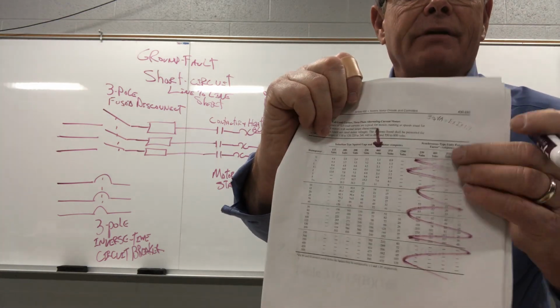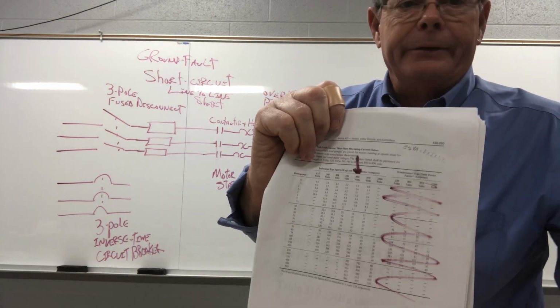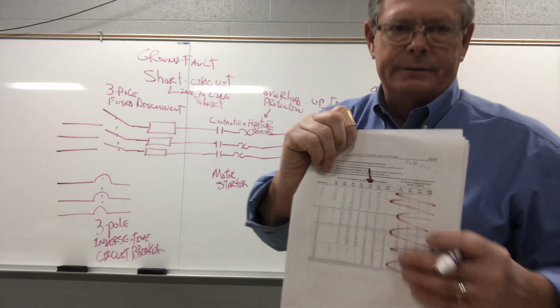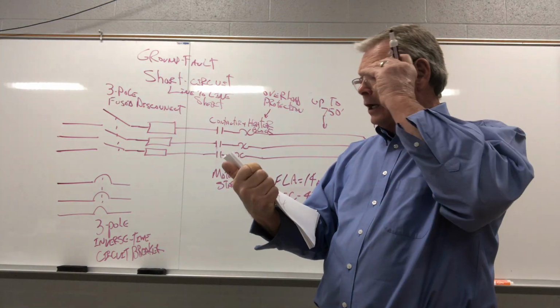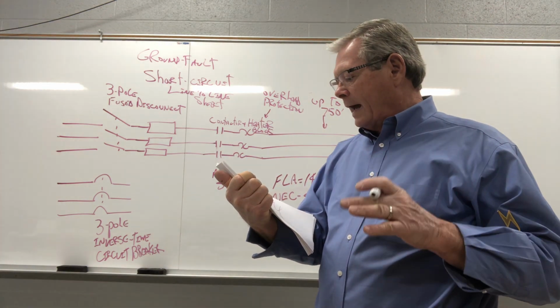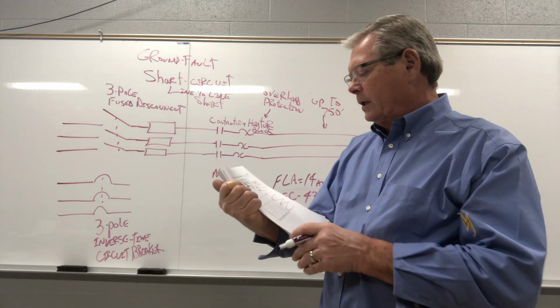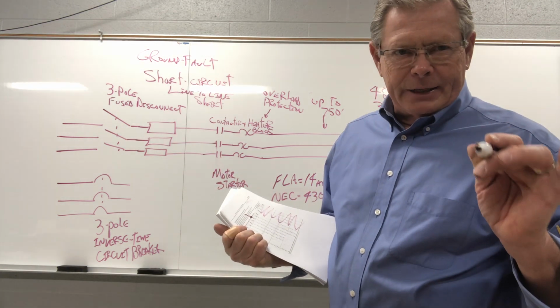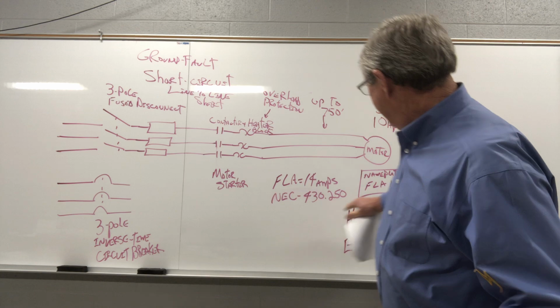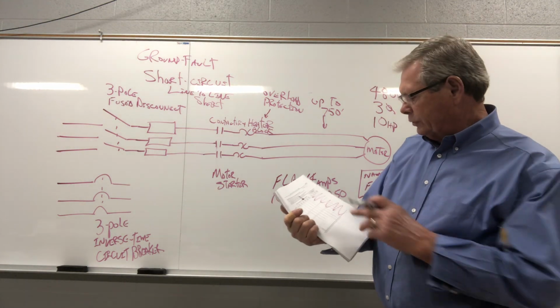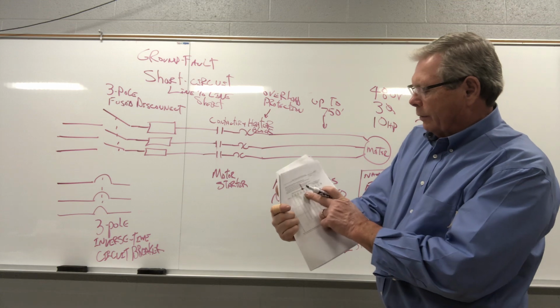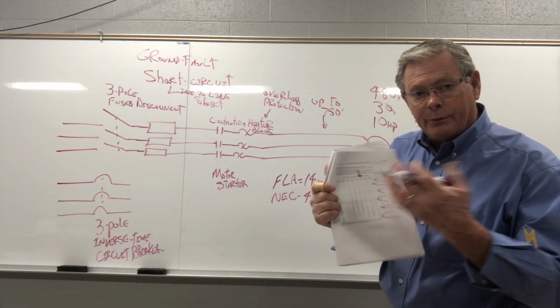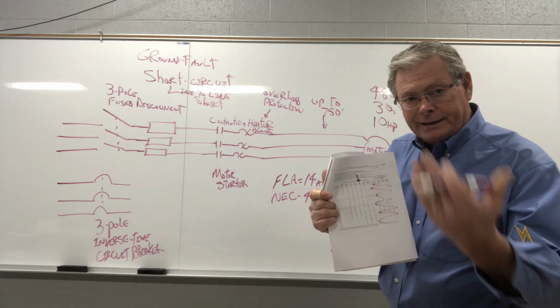This area here that I've got marked out, you don't need that. You just need this side here, okay? It's the side that says induction type squirrel cage and wound rotor motors. So all you need is the application voltage and the horsepower off the nameplate. So it's 10 horse, okay, at 480. So this column says 460, you pick the columns closest to what you got. We got a 480, it says 460, we use the 460 column.